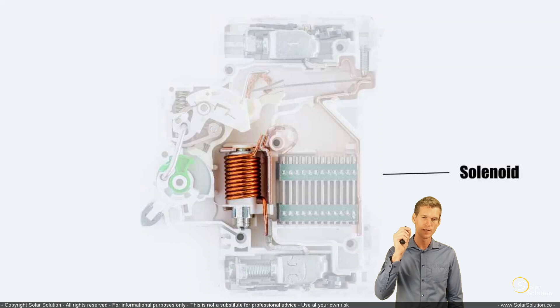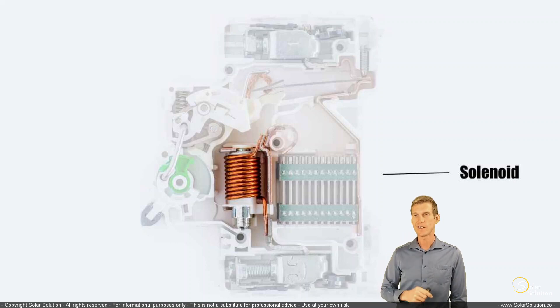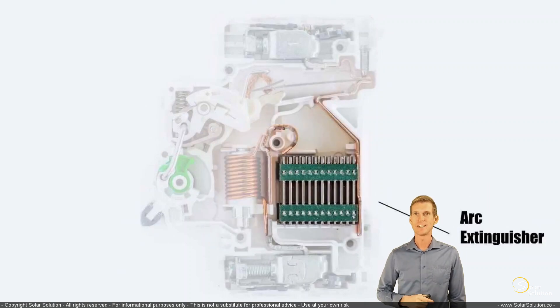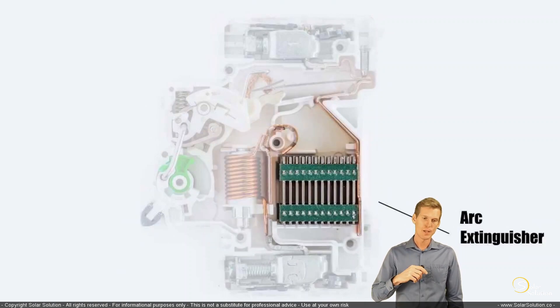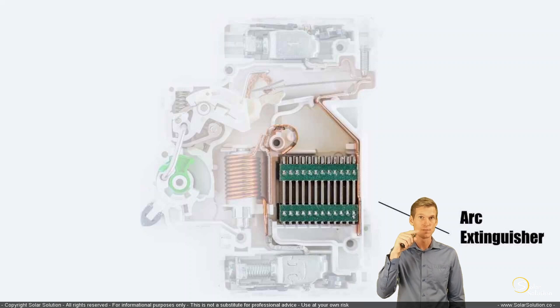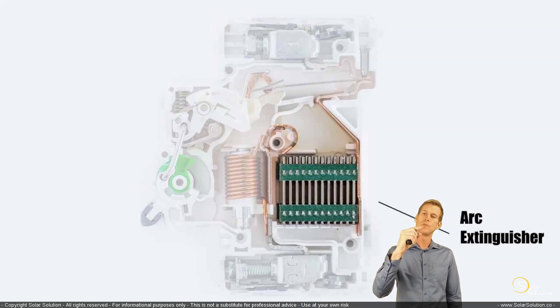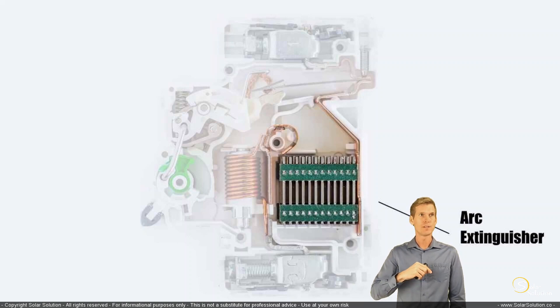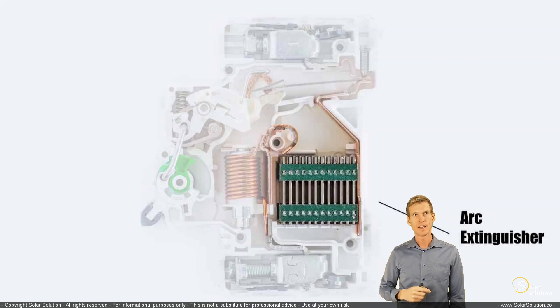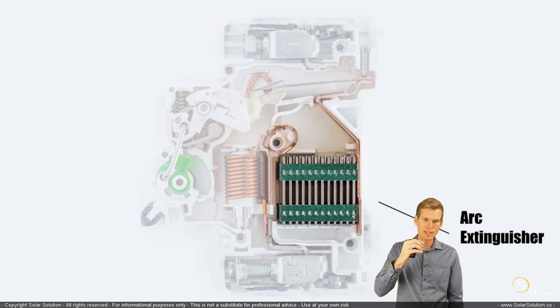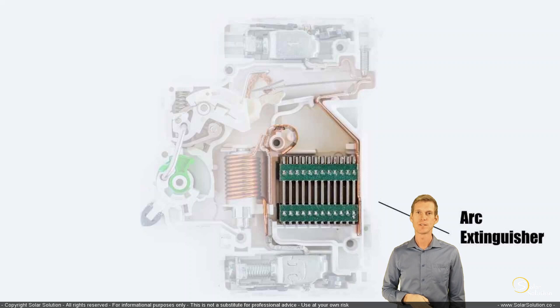Another important component is the arc extinguishing chamber, which does exactly what it says — it extinguishes an arc. When the breaker trips, especially with DC current which doesn't fluctuate, opening the contacts creates a very strong electrical arc — like a little lightning inside the breaker. The breaker redirects that arc toward the arc extinguishing chamber where the energy is safely dissipated and the arc slowly extinguishes by itself.